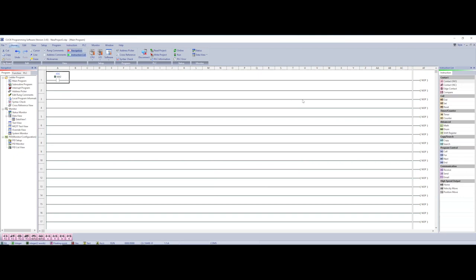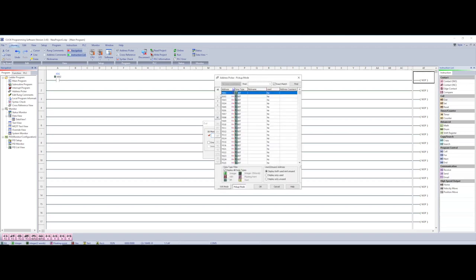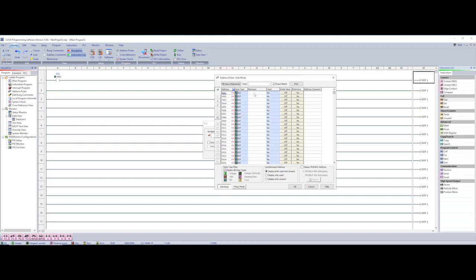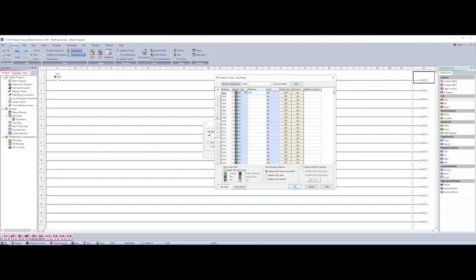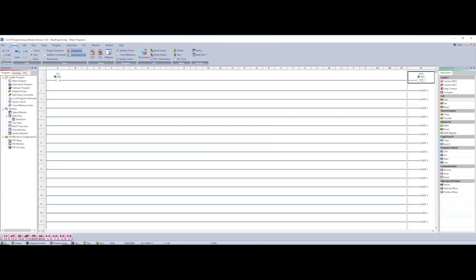Okay now you notice here that the way these rungs are set up I'm going to add my output. Watch what happens. So here's my output. This would be my OTE if I was using Studio 5000. So I go to my output. Automatically it wants to know the address. Remember Y as outputs. So there's my Y. Then I'll go to I'll choose Y1 here which is going to turn on my red light. Now I'm going to edit this and I'm just going to call this run for my nickname. So it's kind of similar to creating tags. I'm going to hit okay. And then you notice you can do a one shot or immediate. You got some different options there. But notice what happens. It automatically turns my NOP on my output side into my output. Right. So again that's super simple.